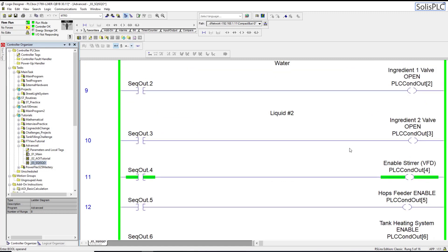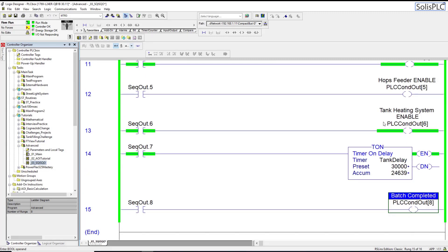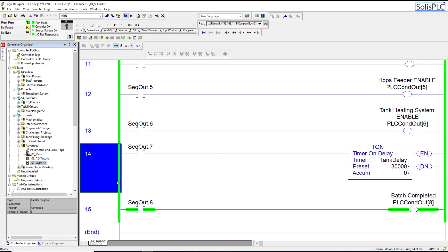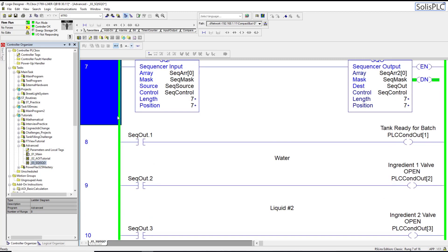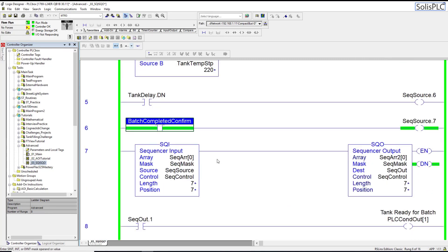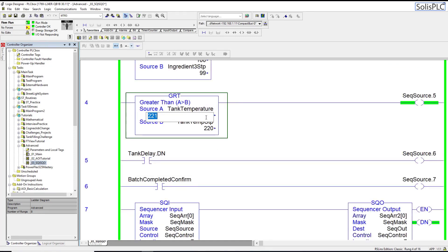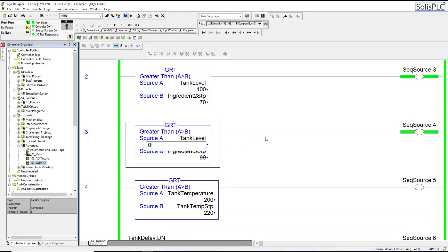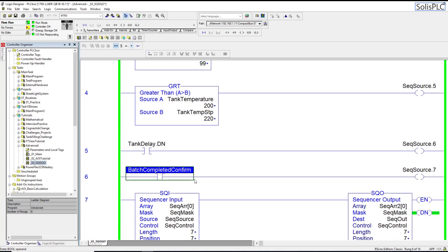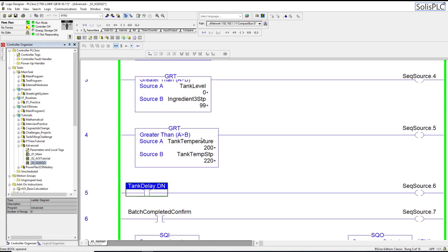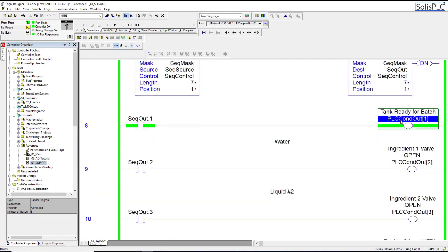Once the 30 seconds are done we should be able to energize the done bit instantaneously and move to the next step - the batch completed process. We're no longer heating, no longer stirring, just waiting for the operator to retrieve the liquid. You can make this even more automated by opening a valve to the next tank, making the process essentially infinite - stepping through all tanks in a line or a belt conveyor. The operator confirms the batch is good, temperature has gone down, and the tank level has been discharged. Once you confirm the batch has been completed we're back into step one where the tank is ready for the next batch.